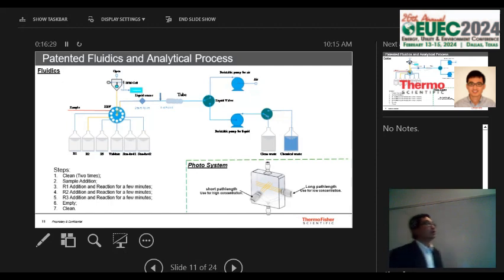In our case, we're not using the peristaltic pump to quantify how much water or how much reagent we are taking in. We only use it as a way to get water, basically a pressure device. So what we do is we take the sample in by switching a rotary valve, a multi-way valve, instead of using multiple single valves. The sample comes in through the rotary valve and this line to the liquid sensor. The pump is just a way to get water through, and once the sample reaches the sample line, it goes to clean waste. Basically, it's just a rinse. You can discharge it anyway.